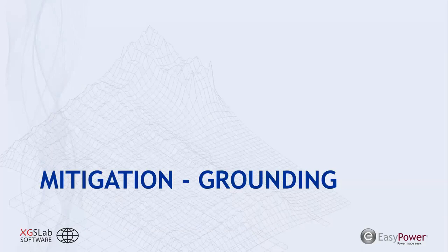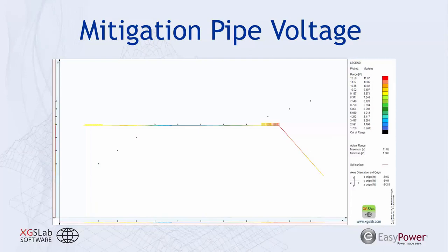So one method we talked about for mitigation is grounding. In this method, I have incorporated about 300 ground rods in order to reduce the voltage that's induced upon the pipeline. And if you recall, our base case had about 28 volts induced upon the pipeline. We're able to reduce that to about 12 volts that's induced on the pipeline. And these rods are placed or dispersed on multiple sections of the pipe.